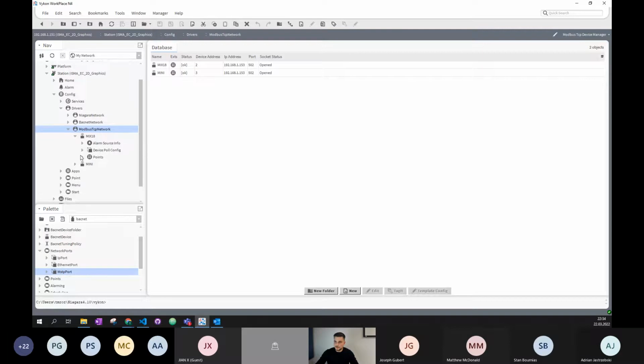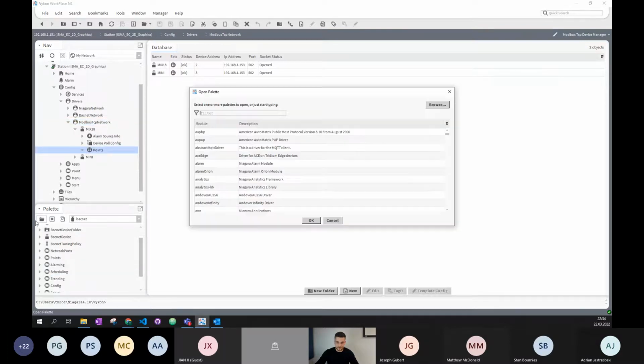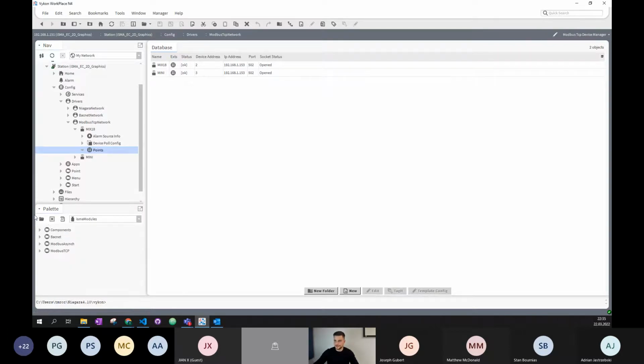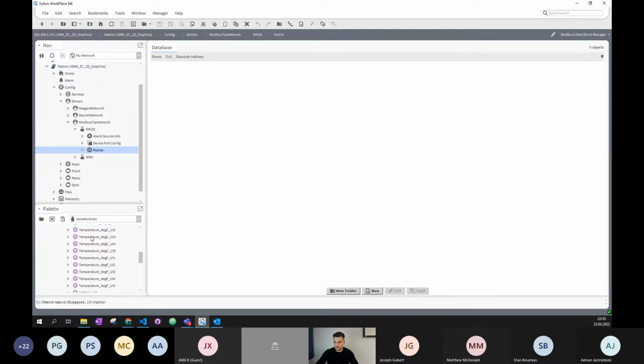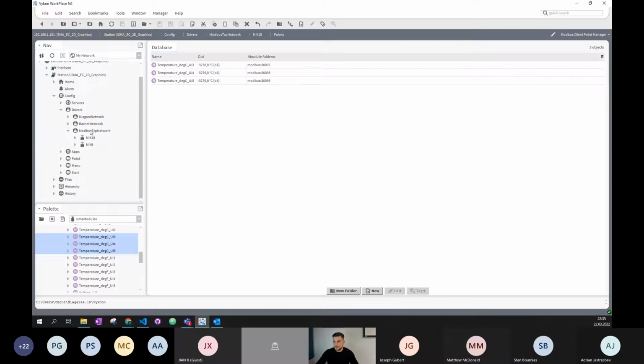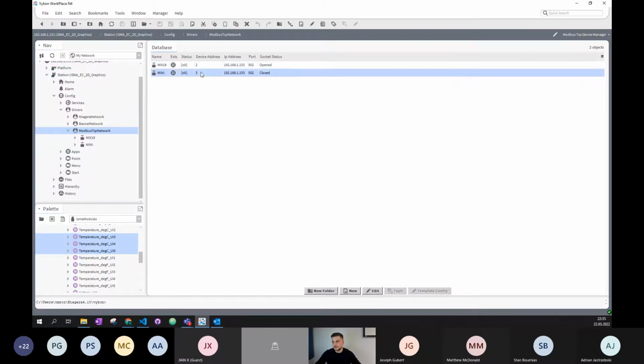If you would like to add the points, you would just do the same steps as I did for the Modbus RTU modules. I go to the ISMA modules, I find the Modbus TCP. I'm using Mix18. I have all sorts of points which I can use. I select which type of measurement and so on. So take this, for example, drag it here, and I have readings from the points. However, there is one issue with this approach. Right now, here we have two connections, 2 sockets open. So each ISMA IO IP module here in Niagara can have only 4 sockets opened at the same time. So right now there is no issue because the number of sockets is 2.